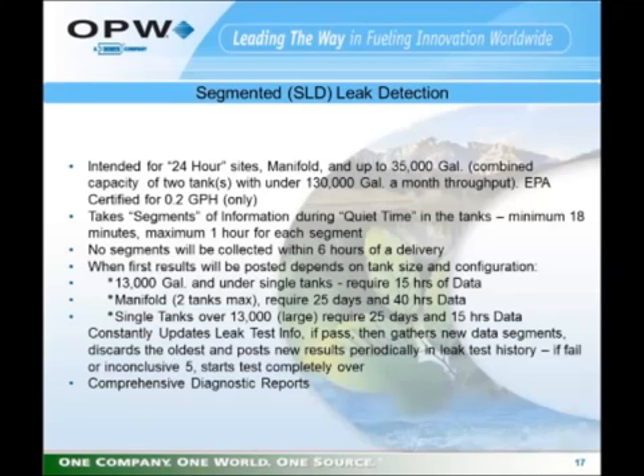Once the database is full, as new data is collected, older data will be pushed out of the database, so the database is always a rolling current tank information. Should a leak test fail, or should a leak test generate an inconclusive 5, and I will explain an inconclusive 5 in a later slide, it will then discard all the data in the database and begin again. With the SLD option enabled, there are comprehensive diagnostic reports that are available, and when you look through the printed materials that are supplied, you'll be able to see the commands to issue those diagnostic reports.